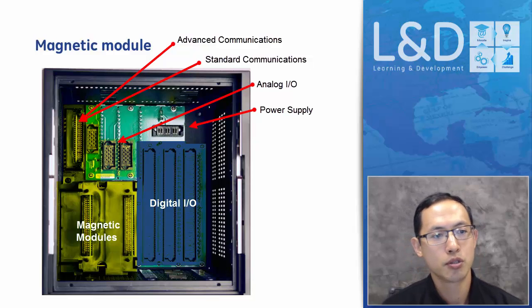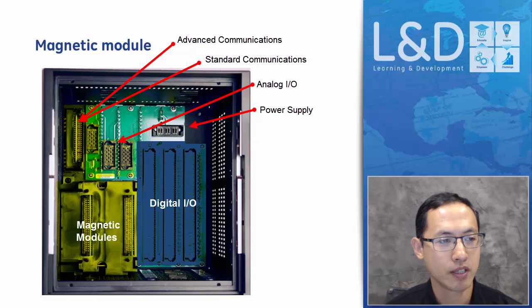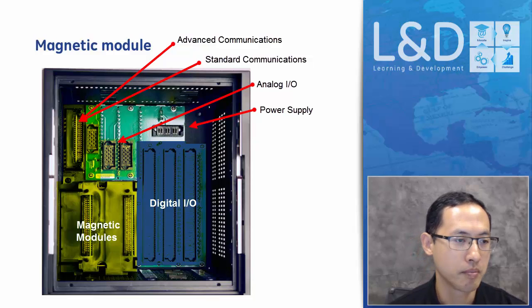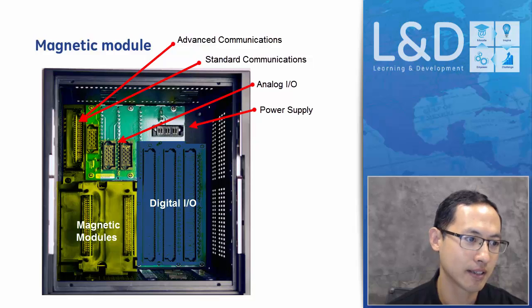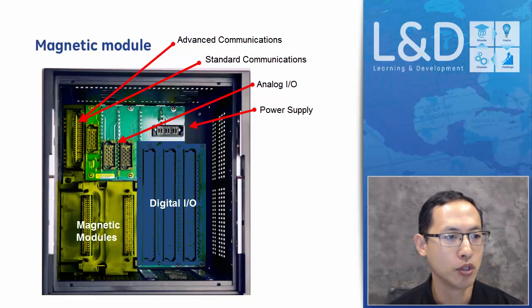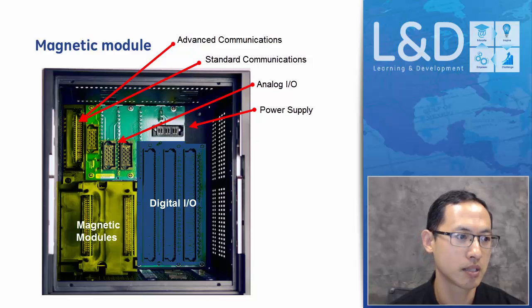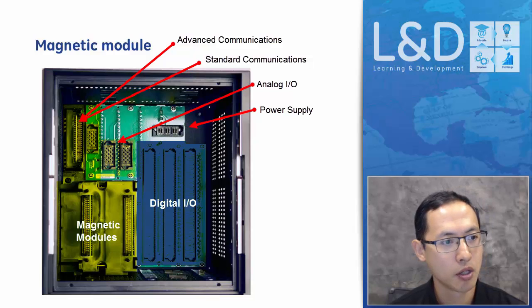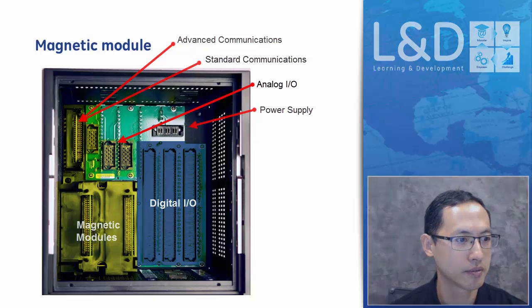In the traditional SR relays and even UR relays, we're using short circuit bars to protect against CT opening. And in the SR3 series and 8 series, we're using the magnetic modules. Once the relay is pulled out of the case, the magnetic modules stay inside the case, so there'll be no open circuit for the CTs. So that's a protection for the open circuit of the CTs.